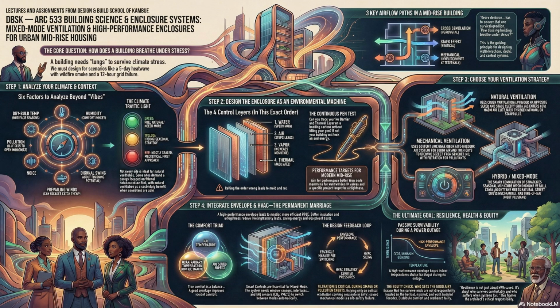And the third, the zonal strategy, which integrates that whole traffic light concept directly into the controls. This is maybe the most difficult to execute, but it's the most responsive. So imagine a building with two different faces. The units facing a quiet courtyard get a green or yellow light. They're allowed frequent natural ventilation. But the units on the street side? The street-facing units are constantly battling traffic noise and exhaust. They are locked into a red light status, and they rely almost entirely on highly filtered mechanical air. The control system has to manage these two zones completely independently.